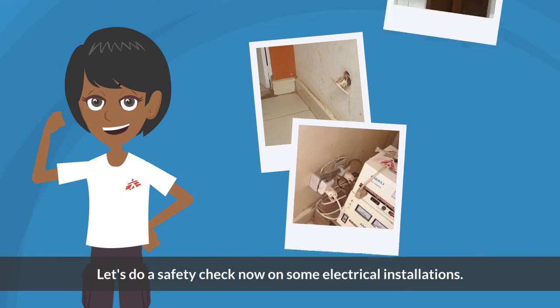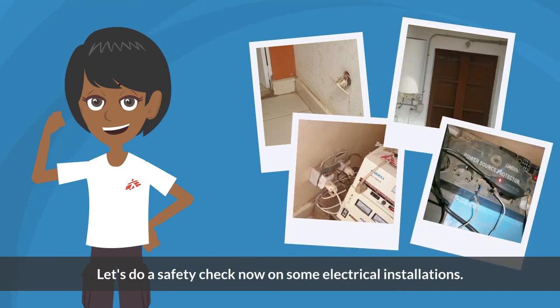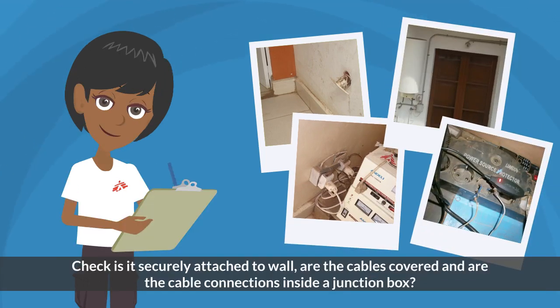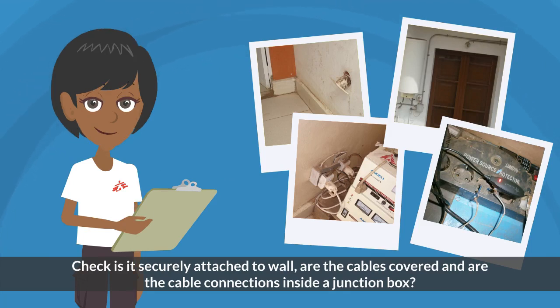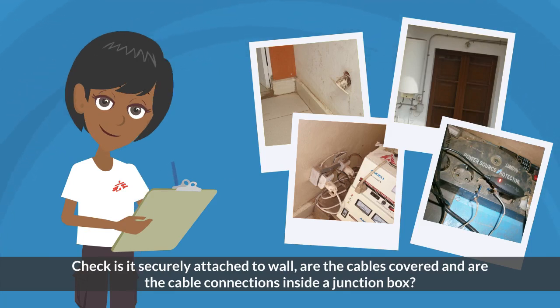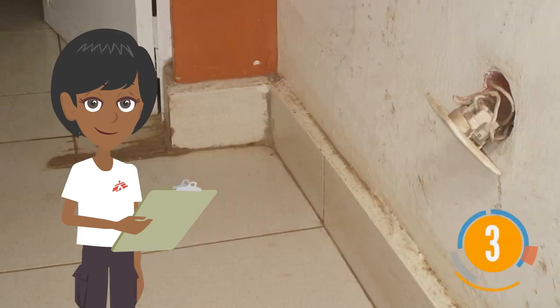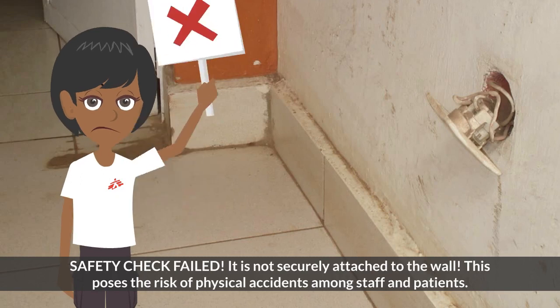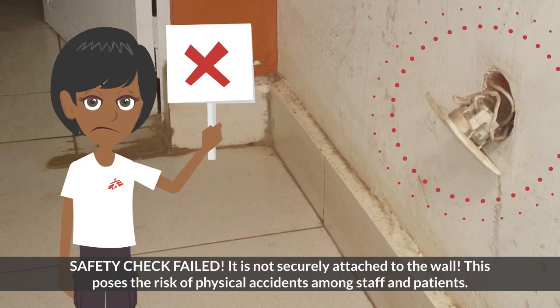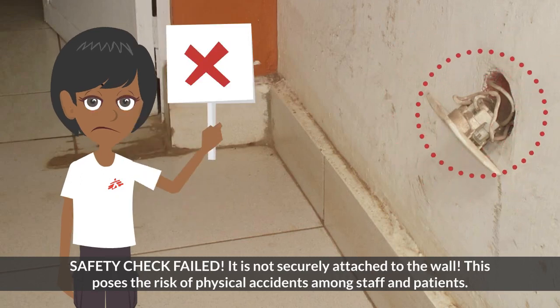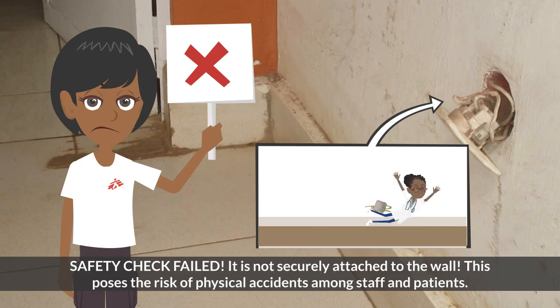Let's do a safety check now on some electrical installations. Check: is it securely attached to the wall? Are the cables covered? And are the cable connections inside a junction box? Safety check failed. It is not securely attached to the wall. This poses the risk of physical accidents among staff and patients.